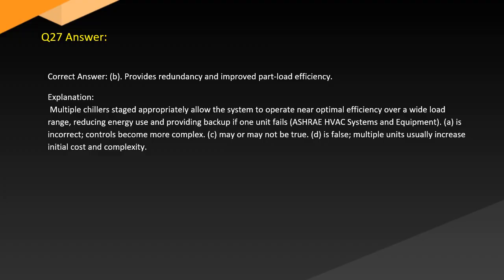Answer. Correct answer. B. Provides redundancy and improved part load efficiency. Explanation. Multiple chillers staged appropriately allow the system to operate near optimal efficiency over a wide load range, reducing energy use and providing backup if one unit fails. ASHRAE HVAC Systems and Equipment. A is incorrect. Controls become more complex. C may or may not be true. D is false. Multiple units usually increase initial cost and complexity.